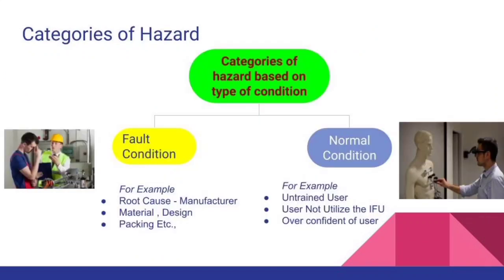Hazards are further classified into two categories: fault condition and normal condition. For fault condition, hazards are caused by manufacturer error — like design failure, wrong material selection on the devices, insufficient packing material quality, and so on. Basically, the fault condition is completely based on the manufacturer side error.